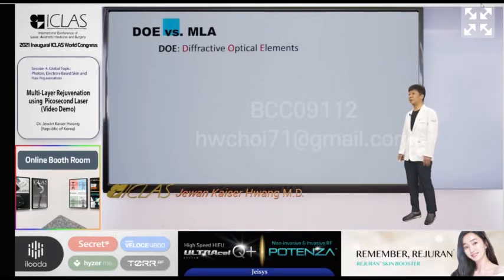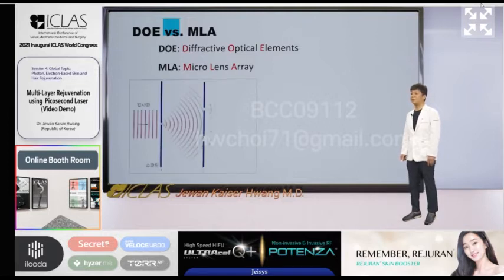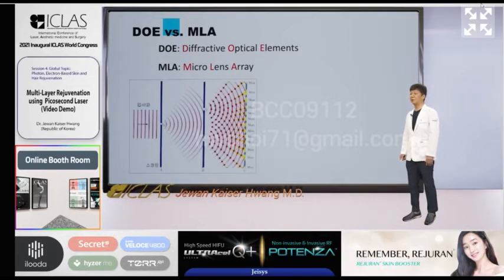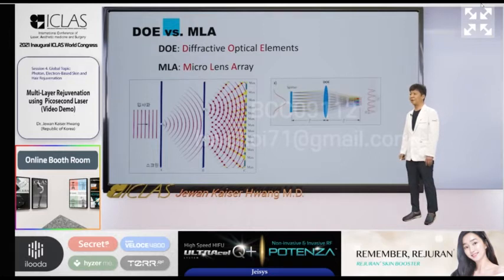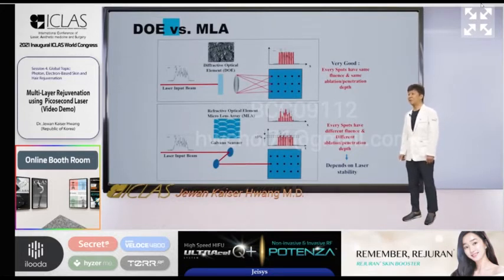Reducing the spot size can increase the power density by making a fractional handpiece, and the spot size of each microbeam can be reduced. There are DOE using diffraction, and MLA using refraction. DOE has the same fluence on each spot, while MLA does not have the same fluence on each spot.